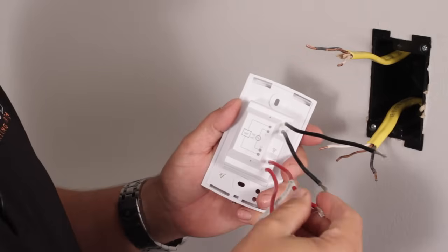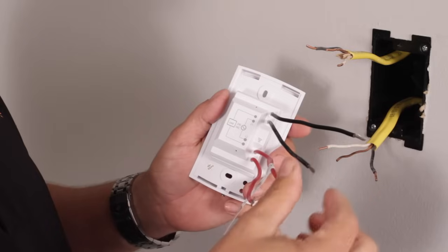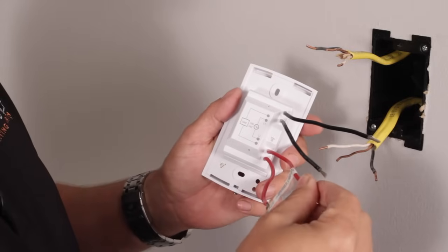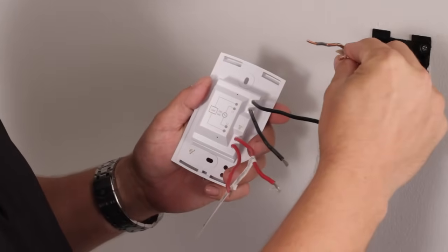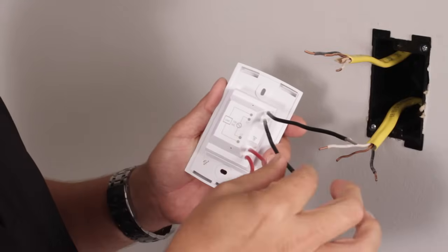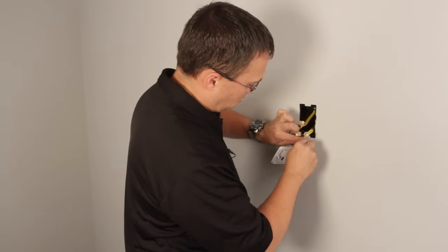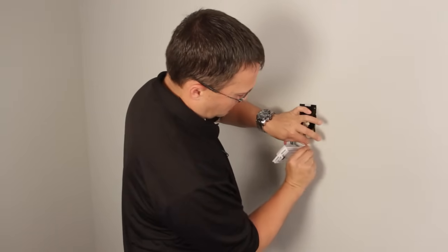Here we have black wires and red wires. The black L1 wire and the red L2 wire are going to connect to the wires coming from the breaker panel. Now the black load wire and the red load wire are going to be connected to the wires going to the heater.